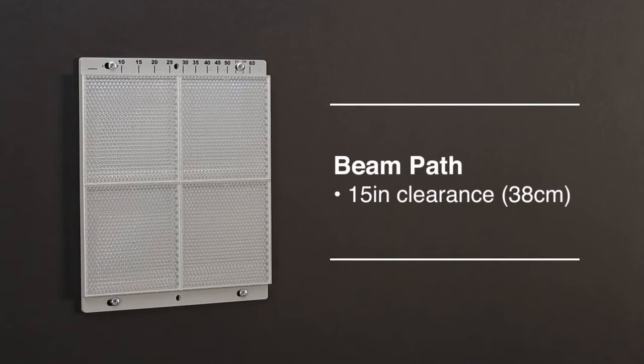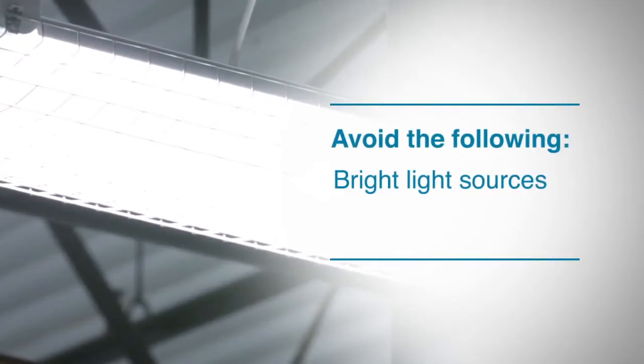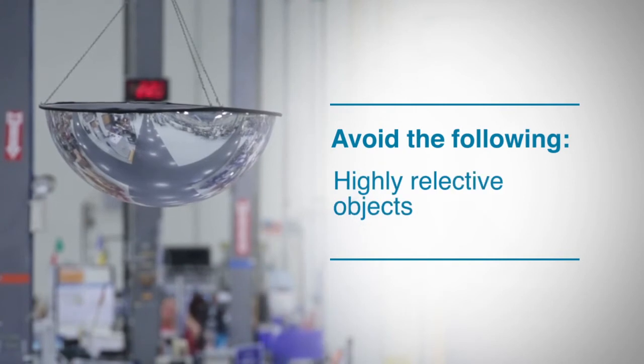Keep in mind that the detector needs a clear path with at least 15 inches between the beam path and any obstructions. Bright light sources or highly reflective objects should be kept away from the beam path, and direct sunlight into the beam or the reflector should be avoided.